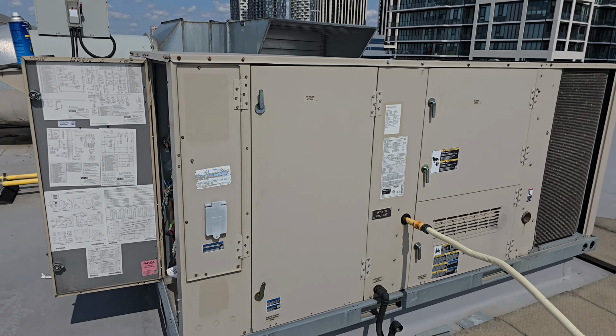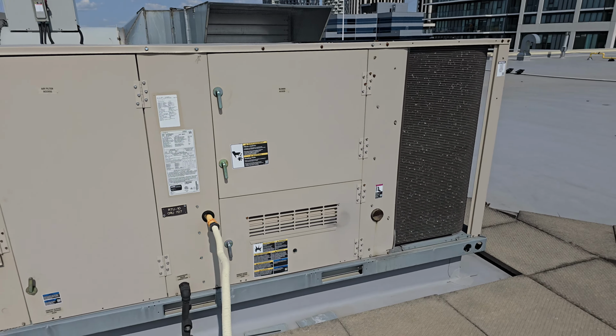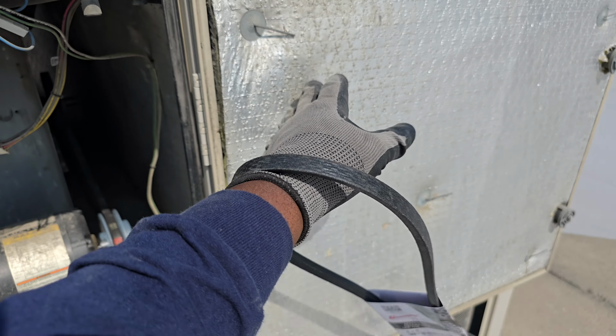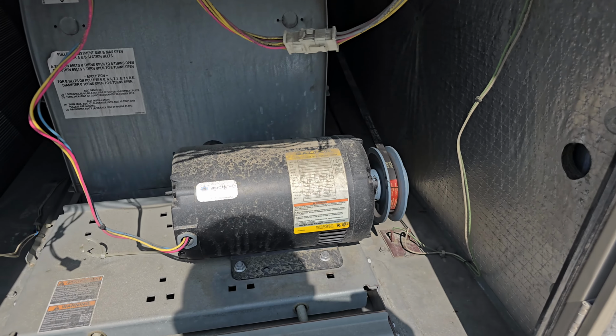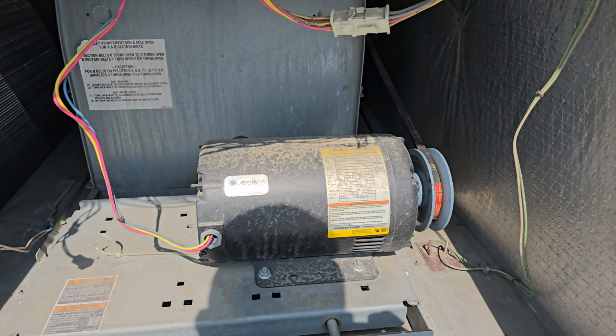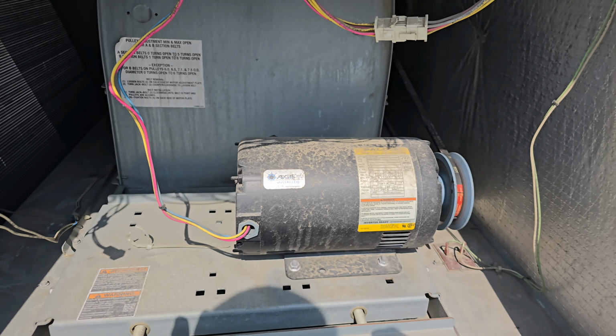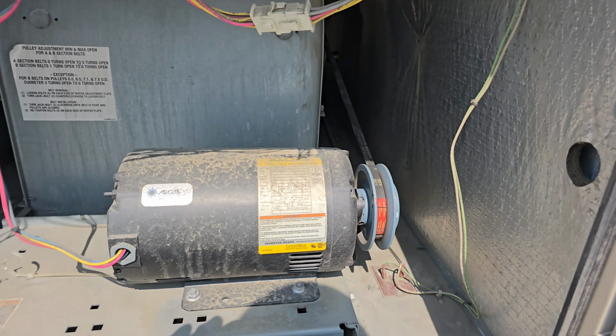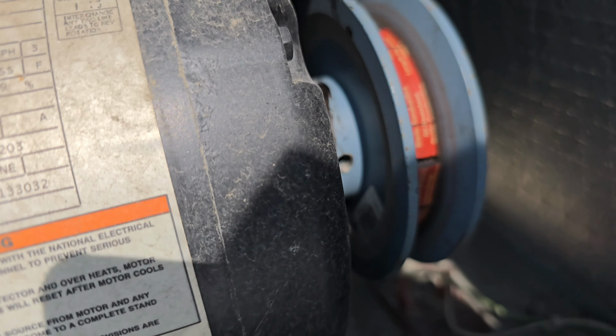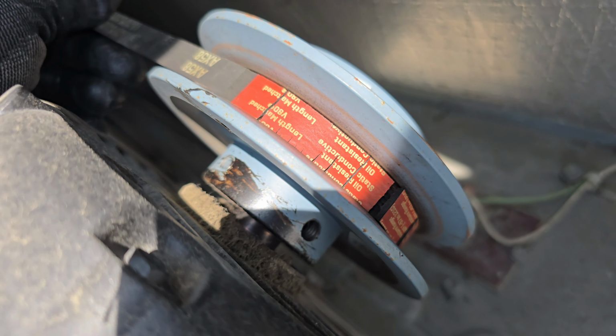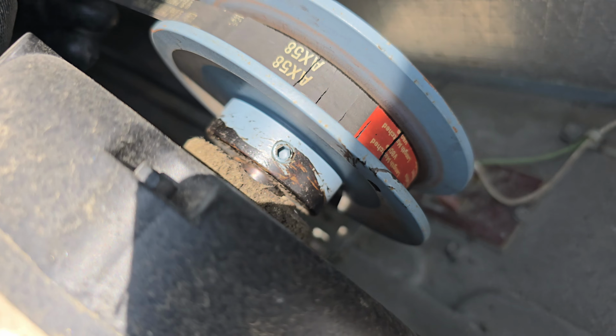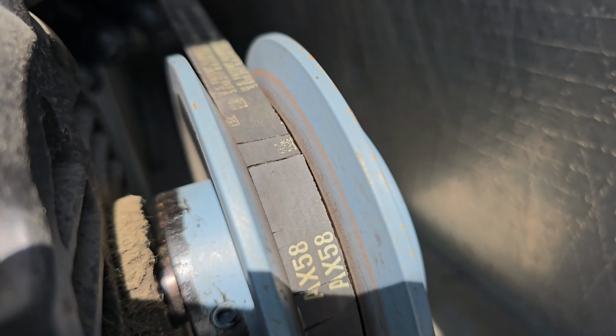Now that my filter is taken care of, I'm going to go to the blower section to check my belt. Remember, your unit must be turned off. Here in the blower section, look at my belt, it's ripping off already. This belt is really bad, you can see how bad it is.